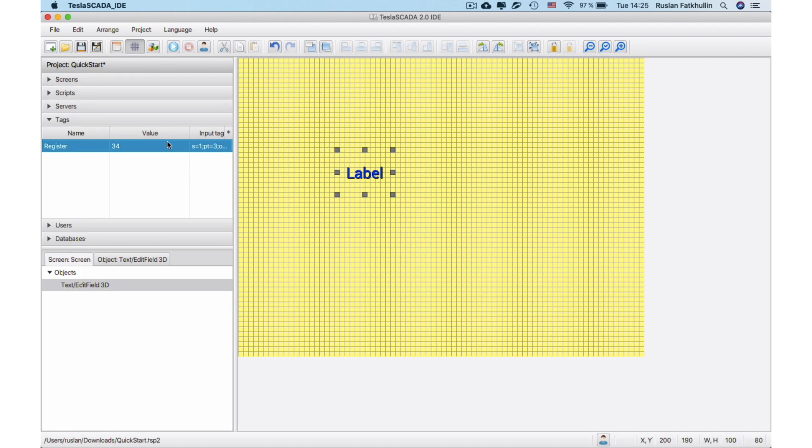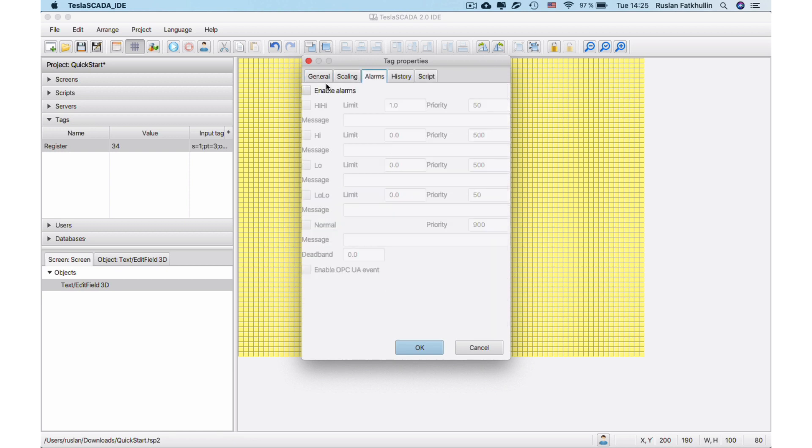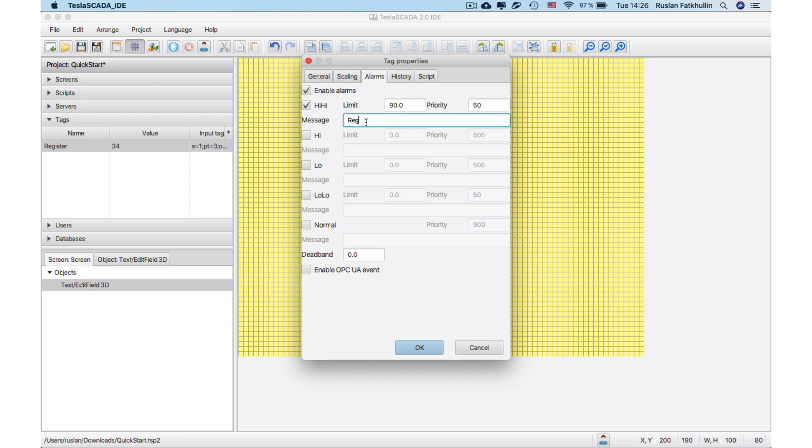Now let's add alarms in our project. To do this, open Tag Properties and choose Alarms tab. Enable Alarms and enable HiHi. Add limit and message. In our example, if tag's value be greater than 90, we'll get message, register's value is too big.